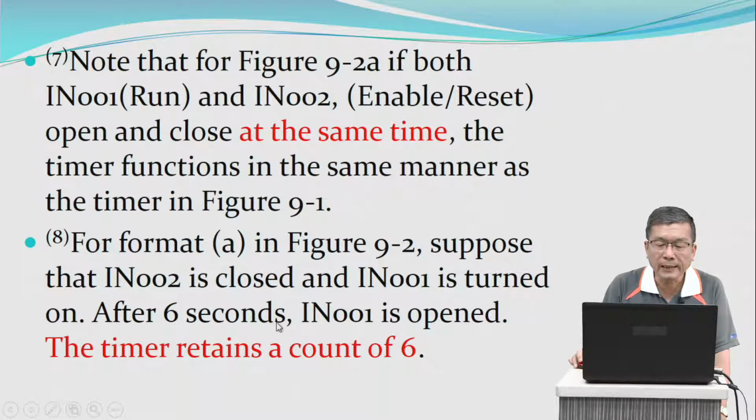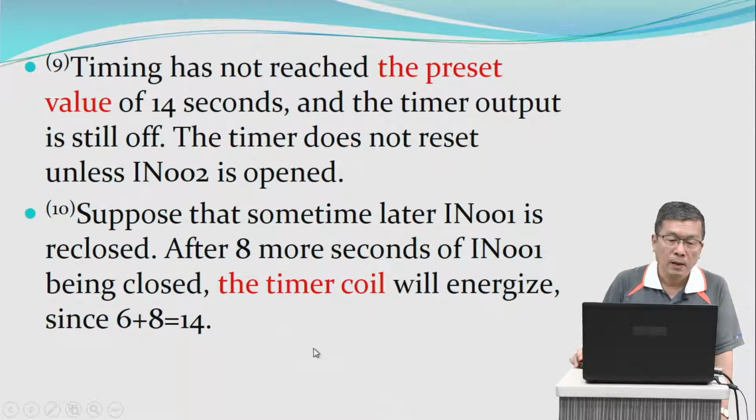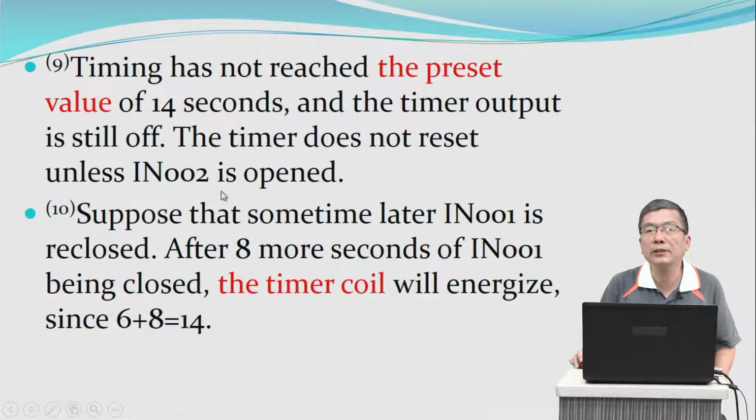After 6 seconds, IN001 is opened. The timer retains a count of 6. Timing has not reached the preset value of 14 seconds and the timer output is still off. The timer does not reset unless IN002 is opened.